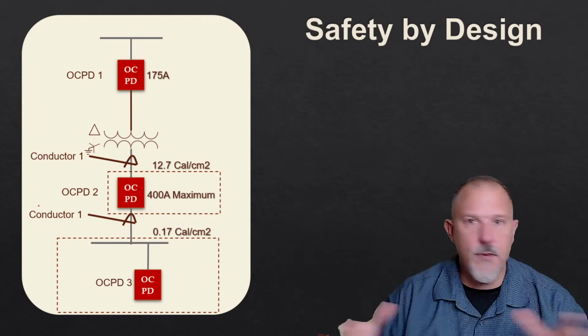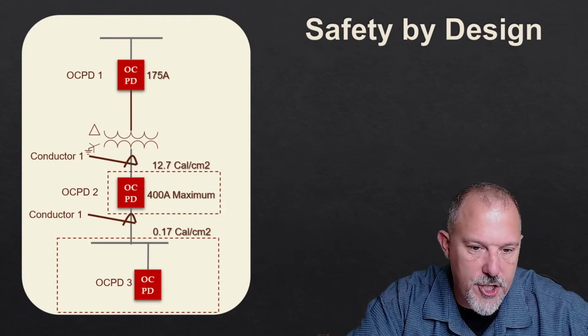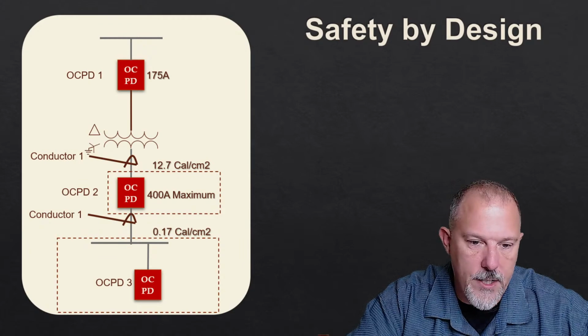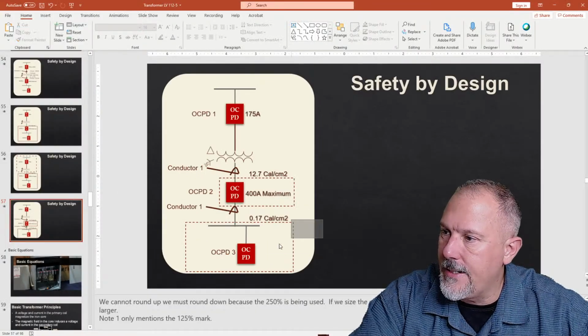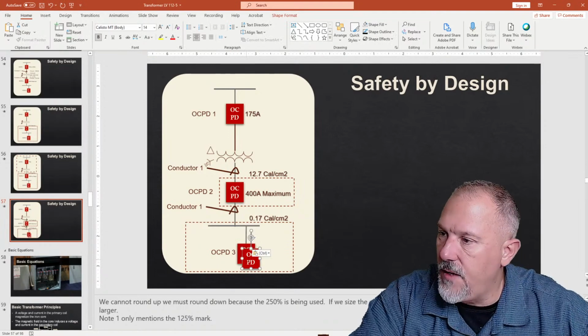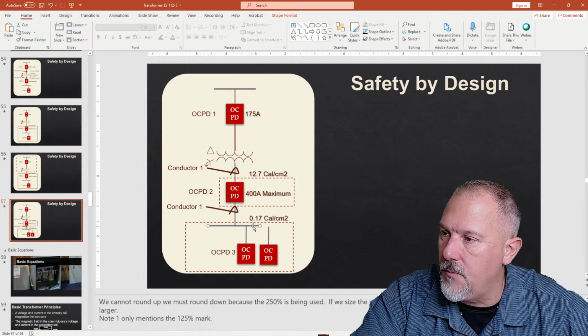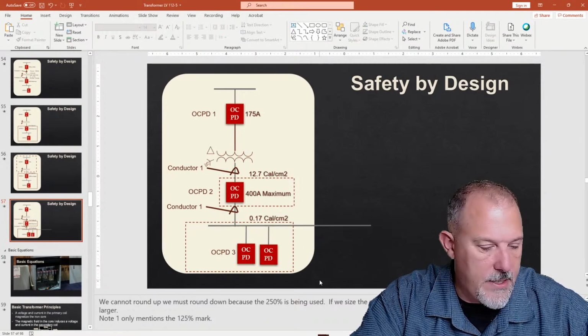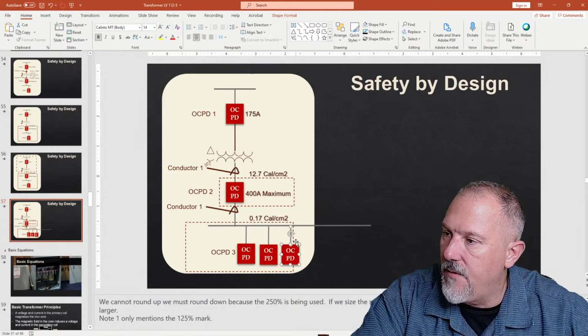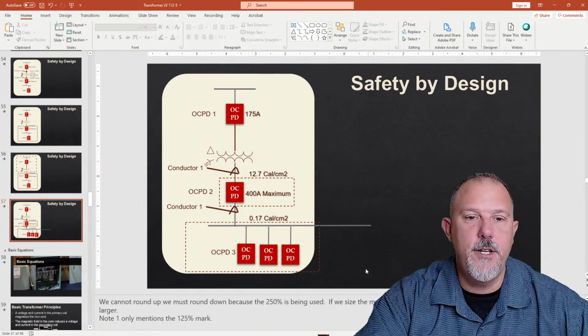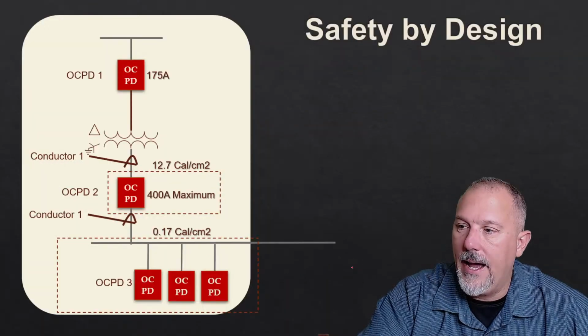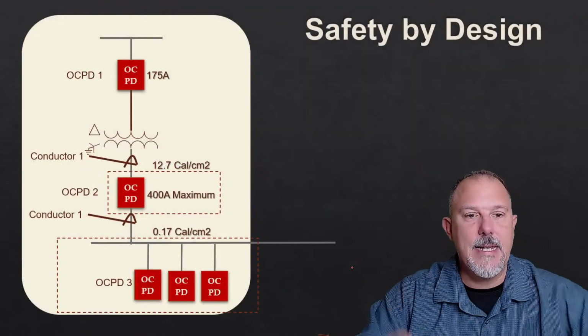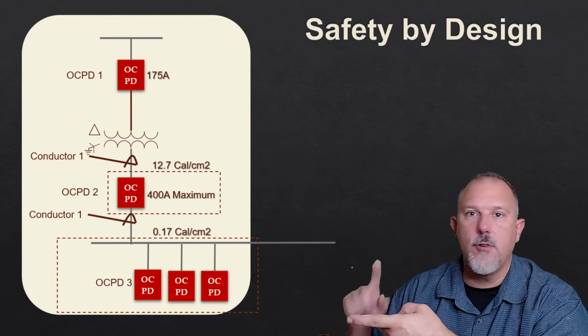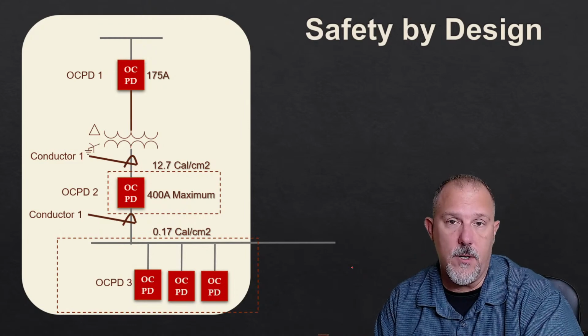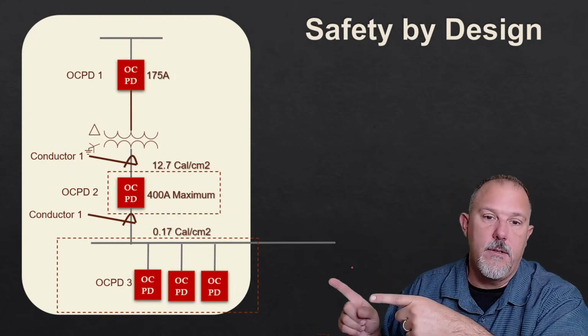In that panel board that has all of those feeder breakers, and what I'm showing is one feeder breaker, which, you know, we can get sassy here and show Control C, Control V. We can say there are multiple feeders in here. There could be 12 overcurrent devices in here. I can have a bunch of overcurrent devices in here. The likelihood of me having to get into this piece of equipment to add a breaker, to do anything, justified energized work, it's going to happen in this piece of equipment.